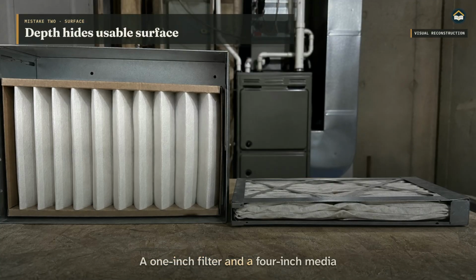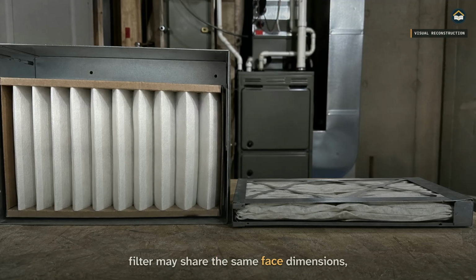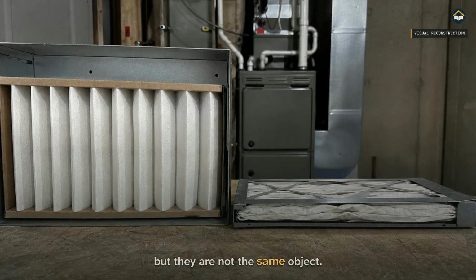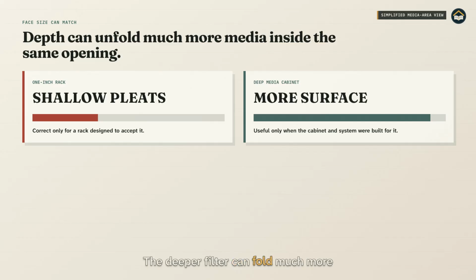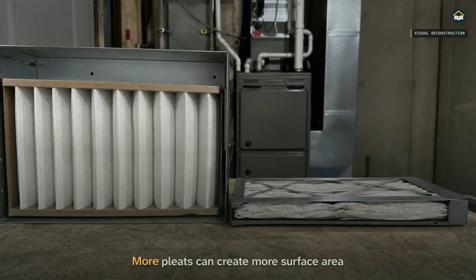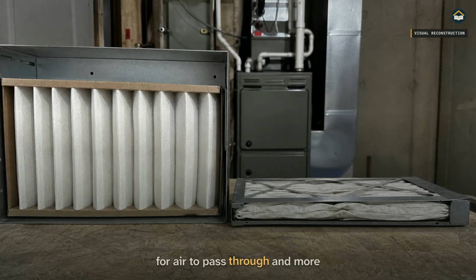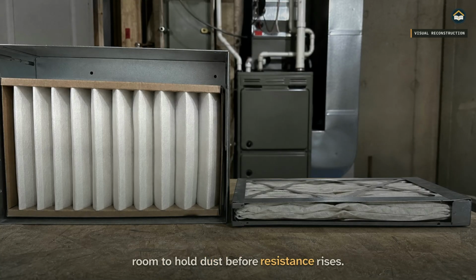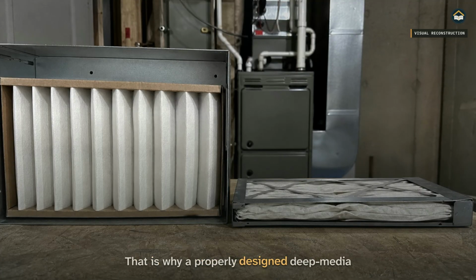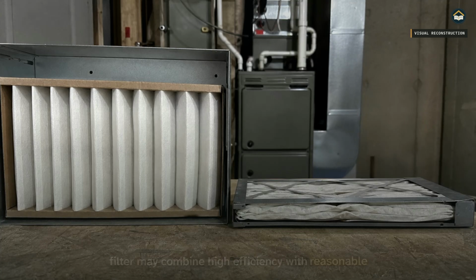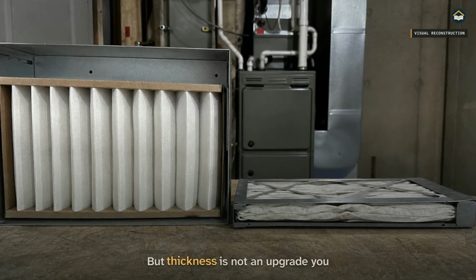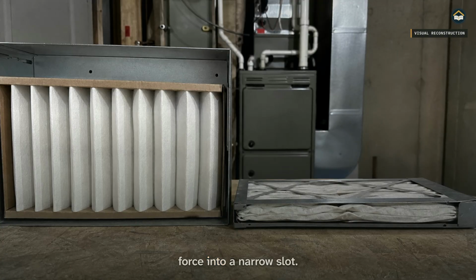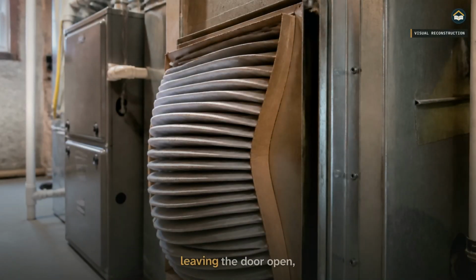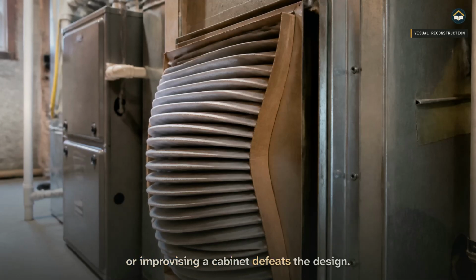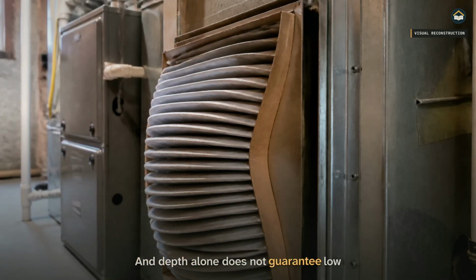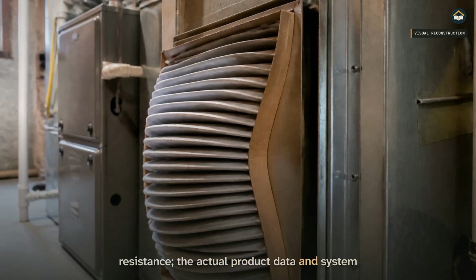A 1-inch filter and a 4-inch media filter may share the same face dimensions, but they are not the same object. The deeper filter can fold much more material into the cabinet. More pleats can create more surface area for air to pass through and more room to hold dust before resistance rises. That is why a properly designed deep media filter may combine high efficiency with reasonable airflow and a longer service interval. But thickness is not an upgrade you force into a narrow slot. Bending a thick filter, leaving the door open, or improvising a cabinet defeats the design, and depth alone does not guarantee low resistance. The actual product data and systems still matter.